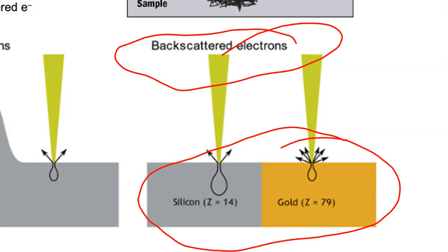So more electron dense elements will stop it, and this concept is actually also very useful in deciding the sample thickness for transmission electron microscopy. That means if you are working on silicon containing compounds, you can afford to take a larger thickness than gold. You can see that gold can stop within a few tens of nanometers, and gold will look darker in transmission electron microscopy.